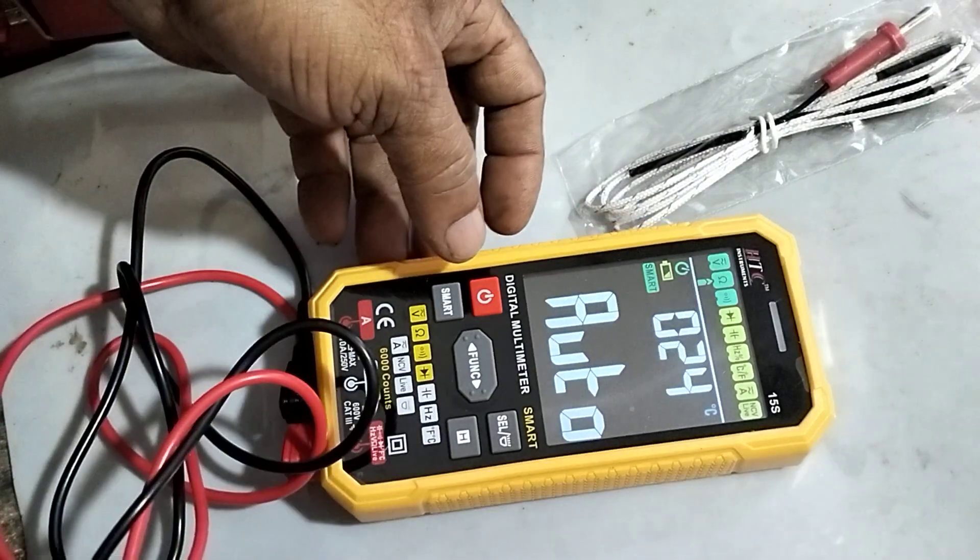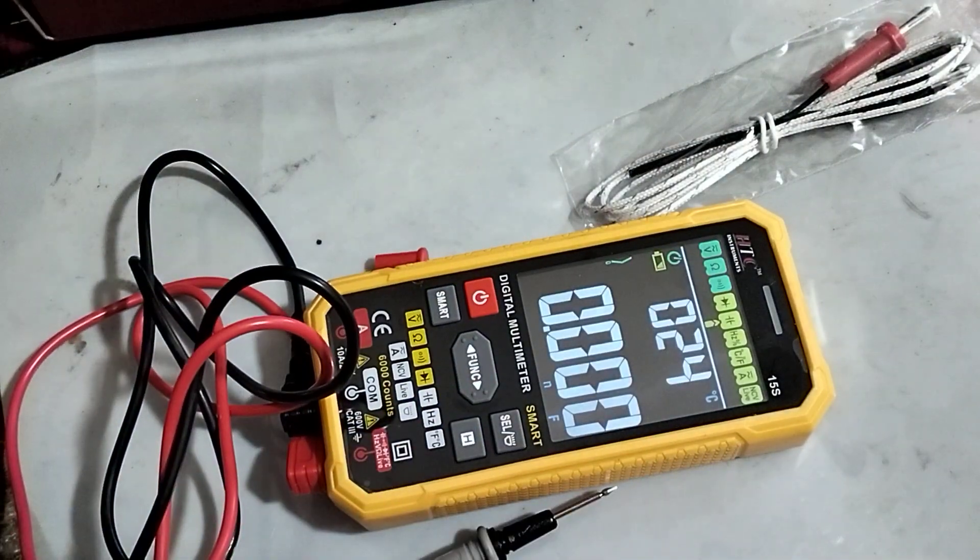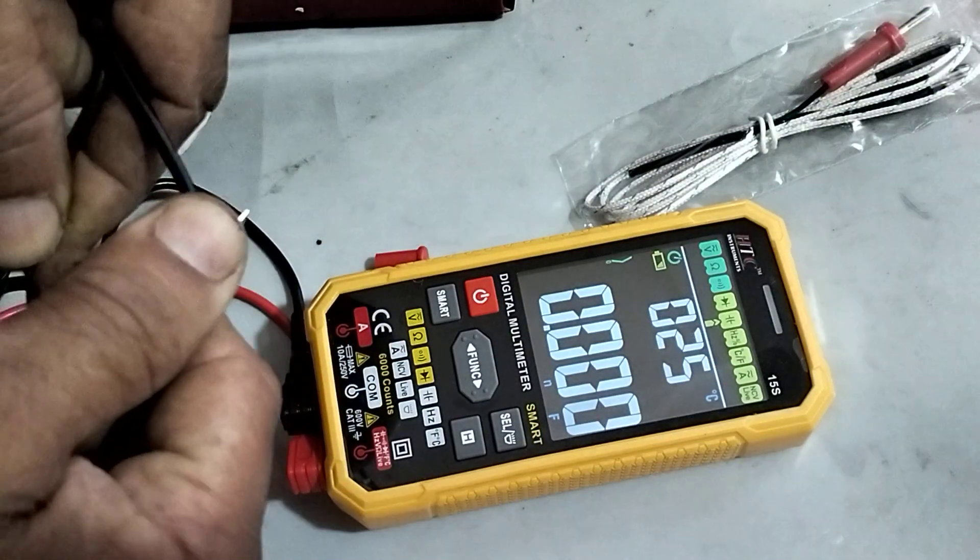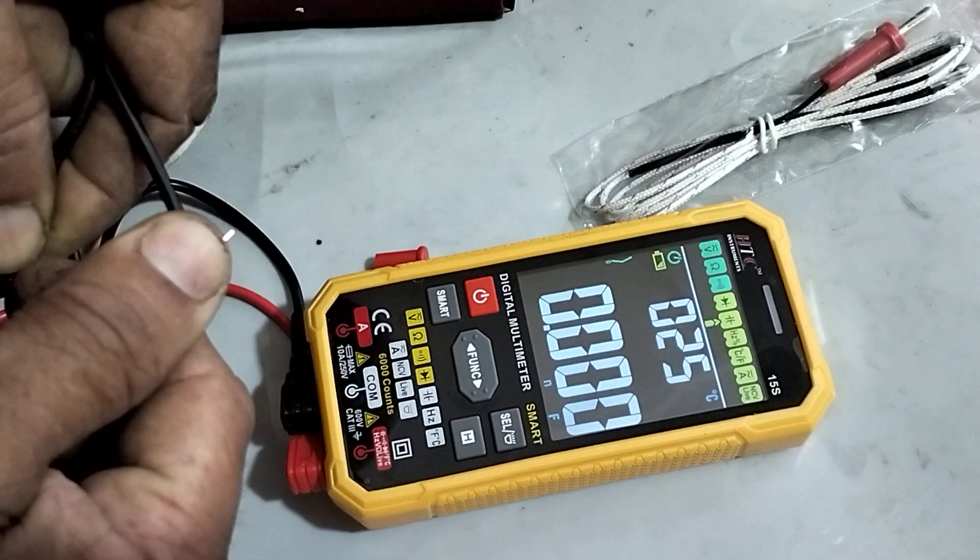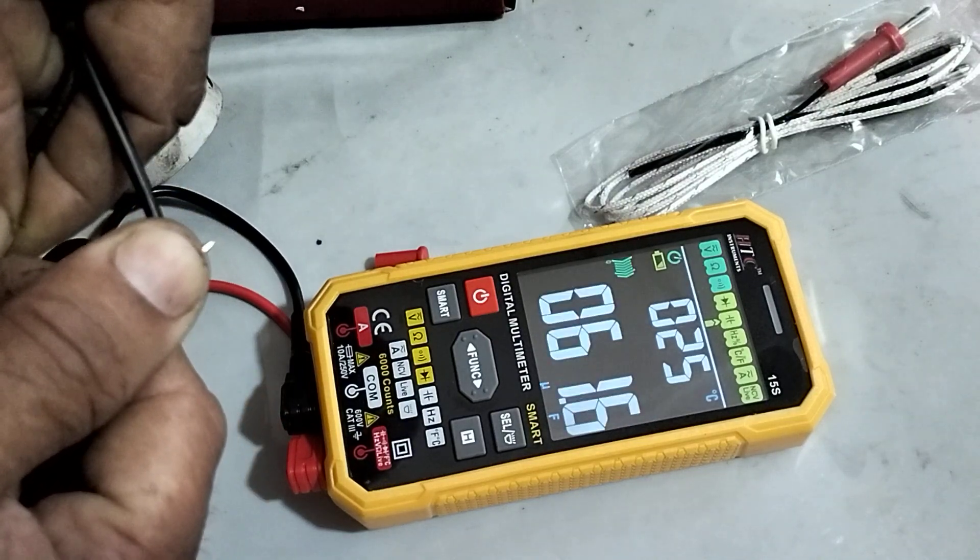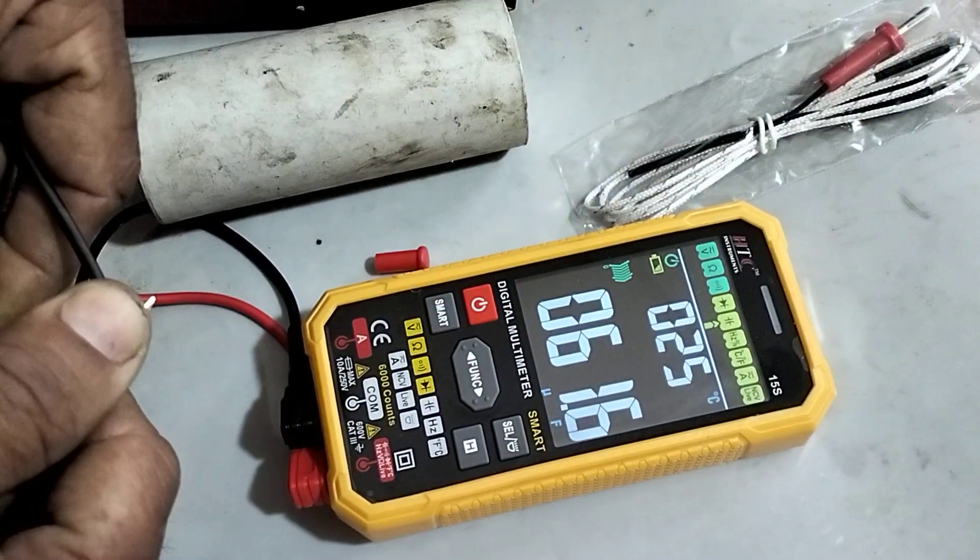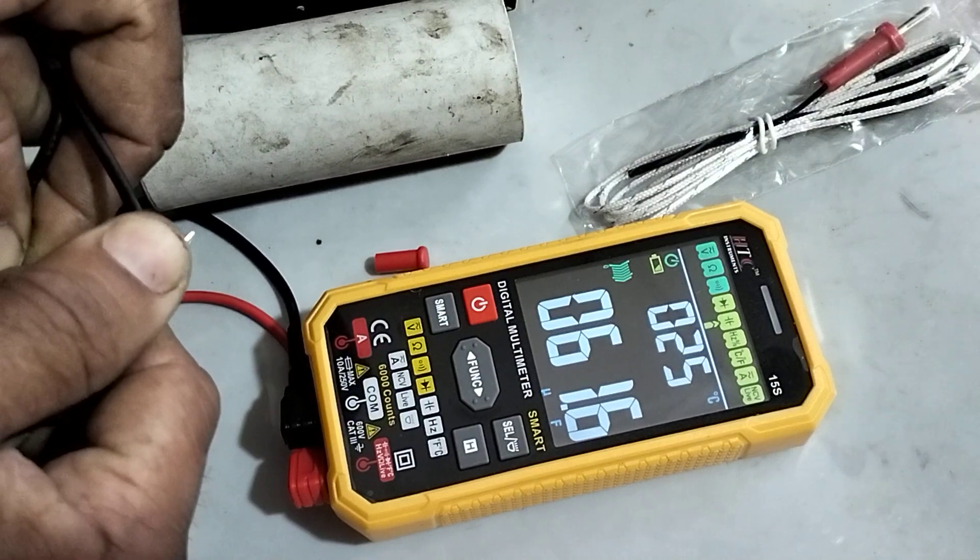If we have to check the capacitor, directly take any capacitor and connect to the lead wire. Now it is zero and then it will sense how much is the value. Okay, this is a 60 mfd capacitor. Now it is showing 61.6.